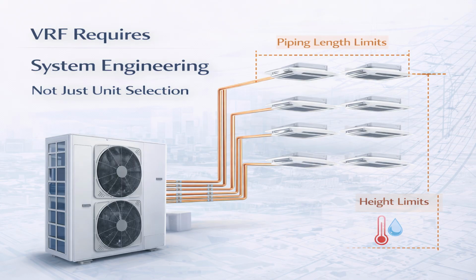A VRF system can be fully approved, installed, and commissioned, yet still underperform simply because the overall system balance was not engineered correctly. When that happens, capacity is unevenly distributed, some zones struggle, others overcool, and the system never operates at its intended efficiency. This is why VRF systems should never be treated as plug-and-play solutions. Their success depends far more on system design and coordination than on individual indoor and outdoor units themselves.